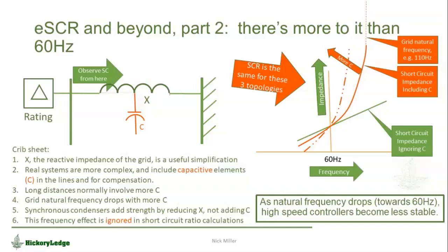Big stiff systems have a natural frequency that might be 200-300 hertz, but long skinny systems have natural frequencies that start to drop down and get relatively close to 60 hertz. And as you add more compensation, or as the system gets weaker, that natural frequency drops more. So that's what the little sketch of the dotted lines show, okay? These three different systems have exactly the same apparent 60 hertz impedance and therefore have exactly the same short circuit ratio, but the dotted orange line is significantly less stable than the green line. Right? So this is a term that you cannot see with your stability programs. You cannot see with phasor analysis, and yet it's a real consideration for the stability of the converters.